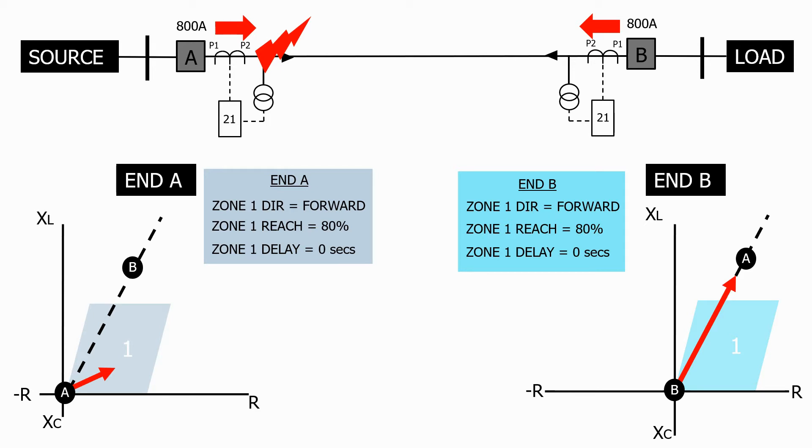But at end B zone 1 only reaches 80% of the line length. The end A impedance relay will now operate, tripping its circuit breaker.